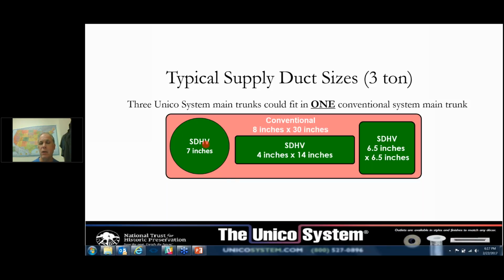Here are the 3 different ways you can run our main trunk. If it's round, for a smaller system, it's 7, 9, or 10 inch diameter round. You can also do it rectangular — a 7-inch round is equivalent to 4 inches by 14 inches rectangular, and the equivalent square would be 6.5 by 6.5 inches. So you can generally fit it in anywhere.